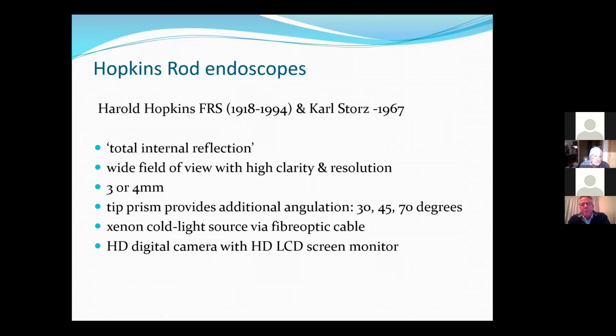If you were to open up an endoscope, you'll find that you have a series of glass rods that are separated by small air gaps, which then provide this system of total internal reflection, where you have this seamless image. Around the outside of the endoscope, you have fiber optic bundles which are transmitting the light from the light source. So they are separate from the image that you see, but obviously do not have the pixelation that you see on a flexible nose endoscope. The advantage is that you have a wide field of view with high clarity and also very high resolution.